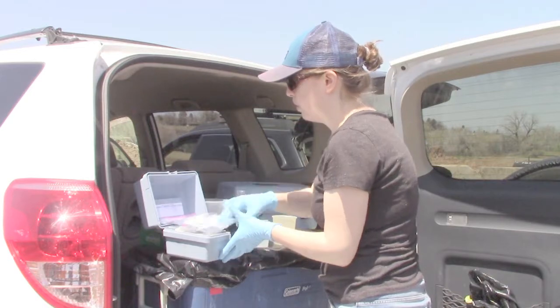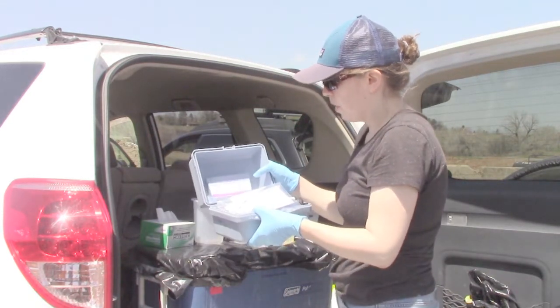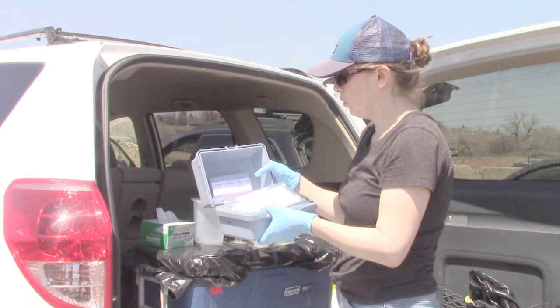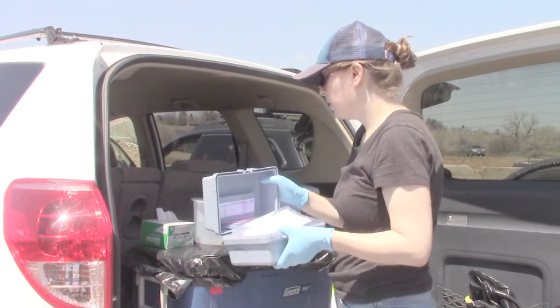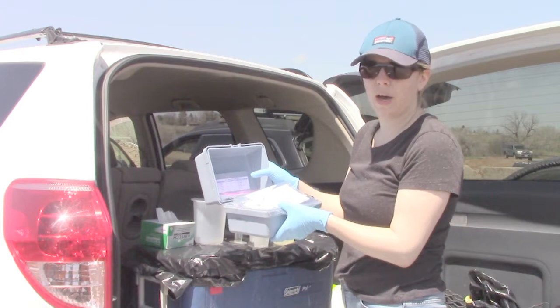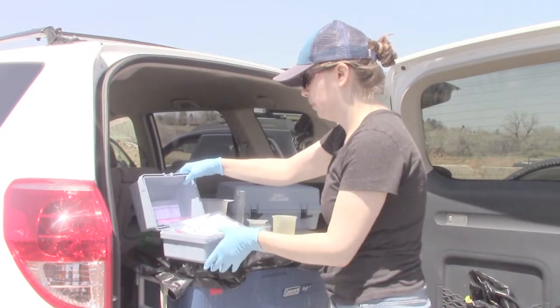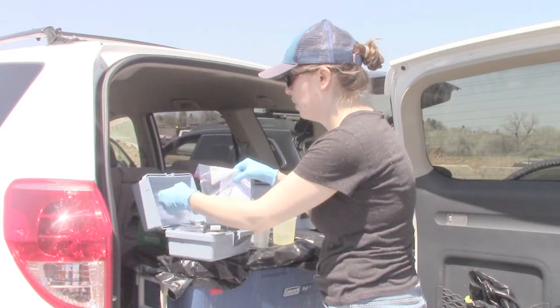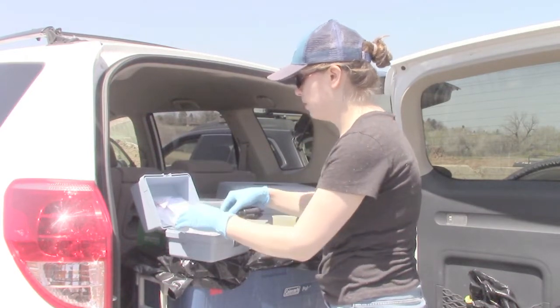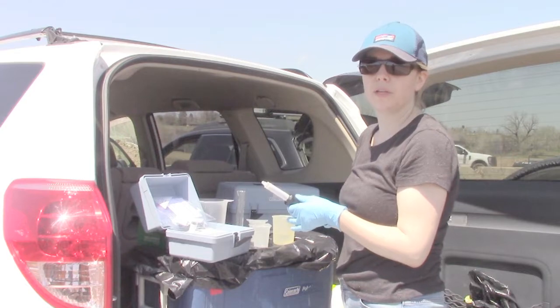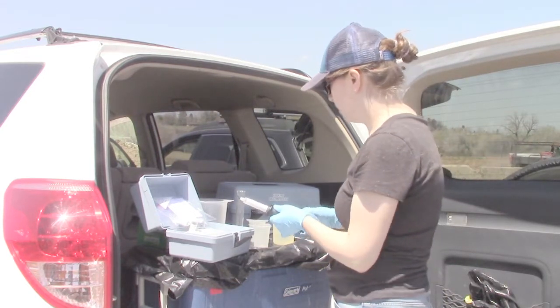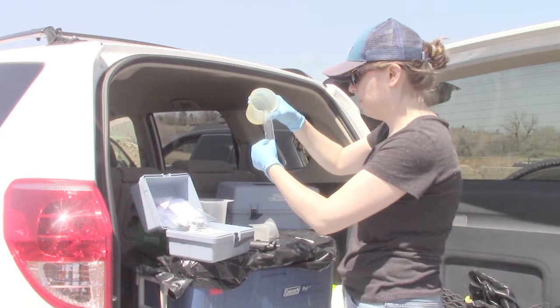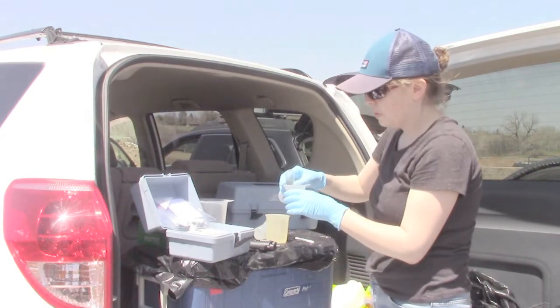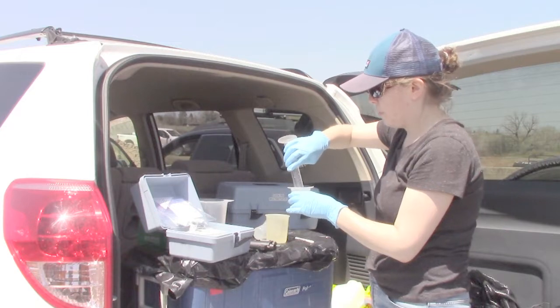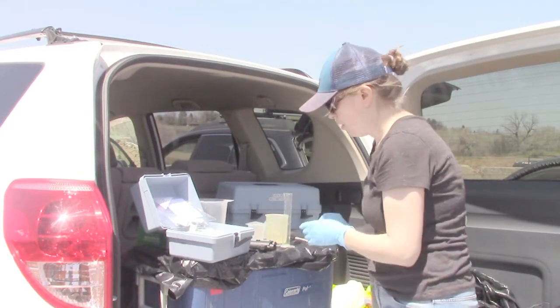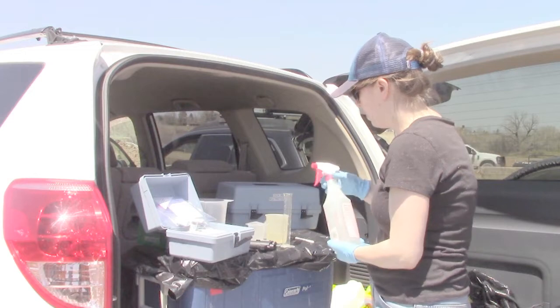What I'm going to do is go with the lower strength cartridge, so 0.16 normal H2SO4, and I'll go with a sample volume of 25 and then fill it up with DI water. That's simply because we've analyzed other samples from Plum Creek today already, so we know that's a good estimate. So I take 25 mils here, pour that into a 100 ml beaker, and then I'll take 75 mils of DI water.